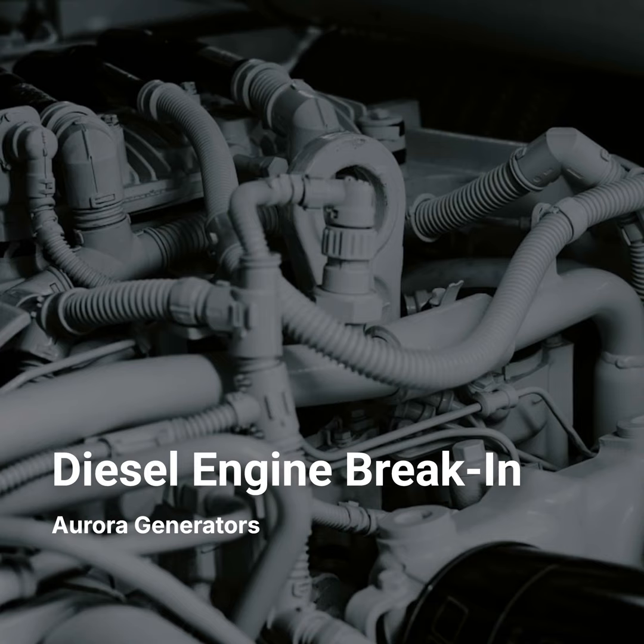If your generator isn't used frequently, you really should treat the diesel fuel with an approved fuel stabilizer. These additives help stop the fuel from degrading and breaking down over time. It's also good practice to periodically test the stored fuel to make sure it hasn't picked up water or gotten contaminated somehow. Good tip.